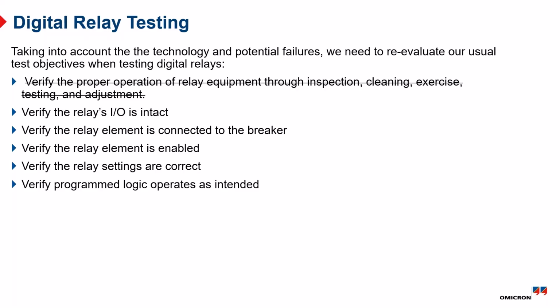Verify the relay elements enabled. I know of one instance in particular that stands out in my mind where there was a transmission line stretching over a Walmart parking lot, and one night the line failed. The line burned down into the Walmart parking lot. Thankfully, it was the middle of the night; no one was there. But the reason is that one phase of phase distance was disabled, and it had been disabled for years.